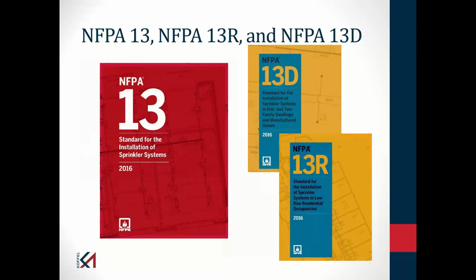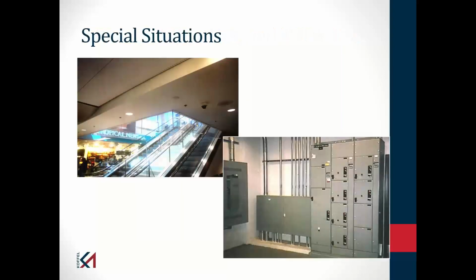Now, there are other special situations. I don't want you to leave this program thinking that the only ones are concealed combustible spaces. If you're being confronted with a question, do I need to put sprinklers in an electrical equipment room? And somebody's arguing, oh, well, electricity and water doesn't mix. NFPA 13 answers that question. And the answer is maybe, or it depends. And it depends upon the type of electrical equipment.